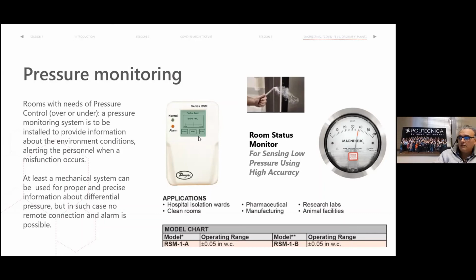This costs more than 10 times than this, and this is one problem. The second is that probably in a retrofit of a hospital, it is very easy to provide a mechanical system. It is maybe less easy to provide an electronic system to be connected to BMS and whatever. So, in general, we use the mechanical one because the solution is very precise. It's even better than the electronic one. There are no problems of electronics that sometimes happen. And so you can choose. If you have money and the BMS is in your hospital, you can provide the electronic one. Otherwise, you can provide the mechanical one.